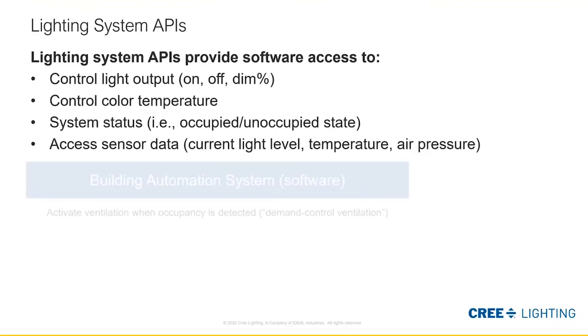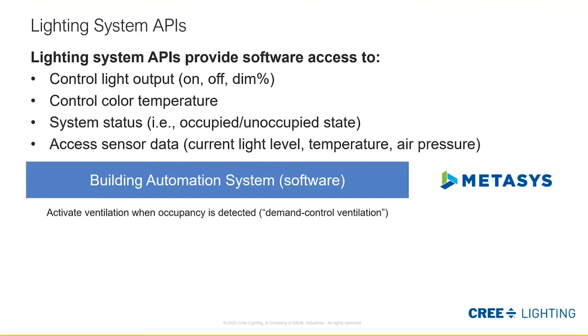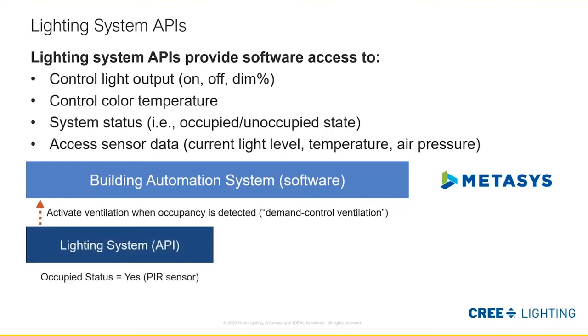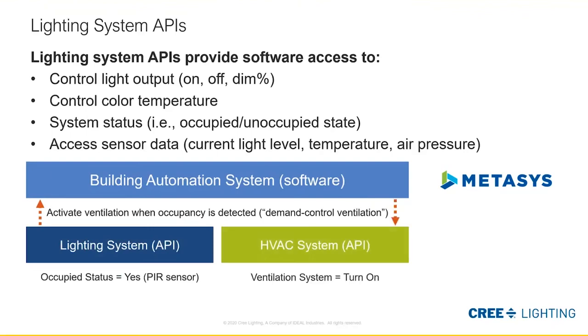One of the biggest applications and lowest-hanging fruit we have is within the building automation system — systems like Metasys, Trane Tracer, or Honeywell. There's a whole market of these systems already installed in buildings, mainly to operate HVAC. A good example: we want to activate the ventilation system in a room when occupancy is detected — in the HVAC world that's called demand control ventilation. Our lighting system API tells us whether the room is occupied, and then the building automation system sends a command to the HVAC system's API to turn on ventilation — opening a damper, turning on ventilation fans — using those APIs to do that.